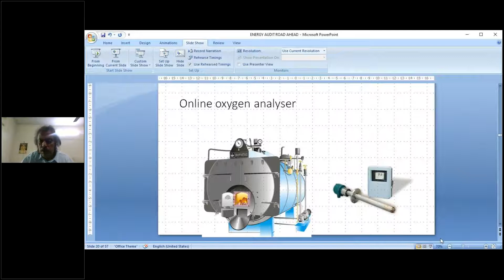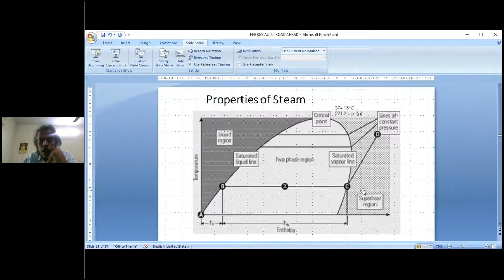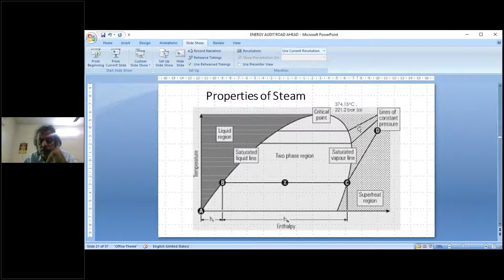The boiler has generated steam, and steam is going to be used in the process, and we need to understand the fundamentals of steam. How steam, why steam, and how much steam, all these questions come into play. As we know, when steam is generated, you have a portion of sensible heat here and latent heat here. It's the latent heat which is actually going to give the heat. Latent heat reduces with increasing pressure. So our objective always should be to use the steam at the lowest possible pressure, so that the full latent heat of steam is utilized. At what pressure you're going to use it and what temperature is required will be determined by the properties of steam.